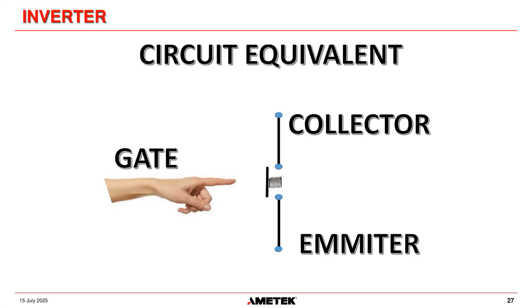Let's go back. When we do press the button, the contacts make and the collector and emitter are connected, so it is now closed. Because it's a spring-loaded switch, if we remove our finger, the switch opens, and unlike an SCR, the connection between the collector and emitter opens as well. So the benefit of an IGBT is we send it a signal, it closes; we remove the gate signal, it opens. We don't have to wait for the zero crossing point, we don't have to wait for there to be no current flowing through it. We have direct control over the gate, whether the collector-emitter junction is open or closed. That is a big distinction between an SCR and an IGBT.